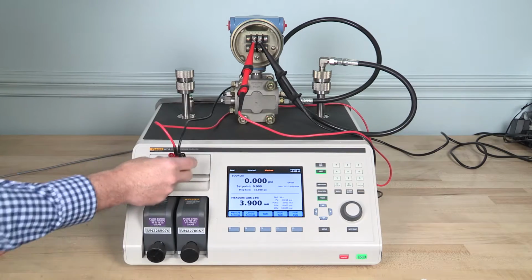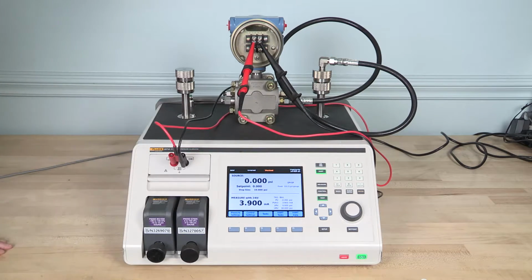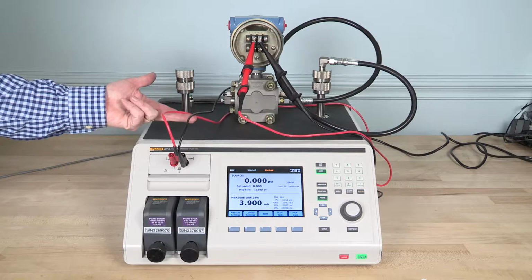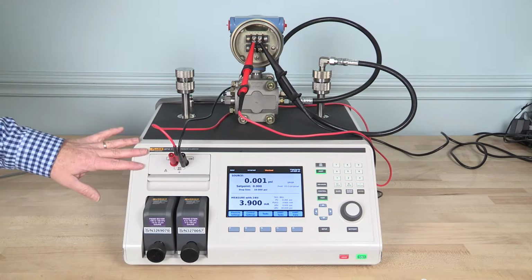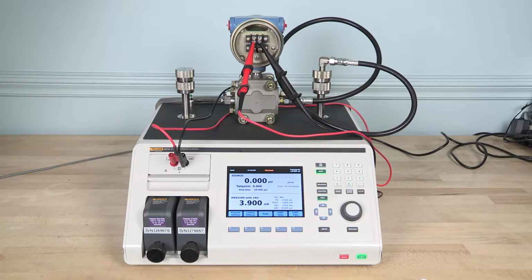We're connected to the electrical measurement module, the EMM over here, and it just takes 2 wires to connect to the HART loop on the unit. There's an internal 250 ohm resistor, so we don't need any external hardware in order to do that. So I'm going to zoom in a little bit closer on the screen so you can see what's going on. We're going to run through an automated task, and we're going to do all this without a computer. So this is automation without a PC connected. Afterwards, we're going to connect up a computer and pull off the data file, and I want to show you how that works as well.